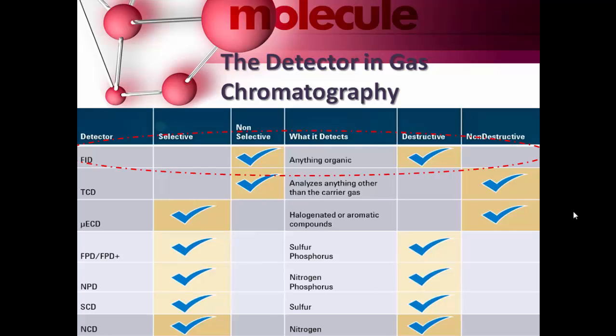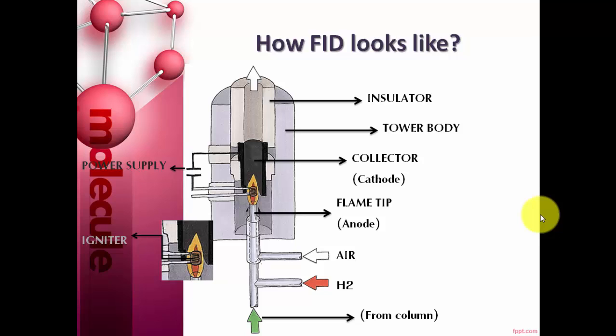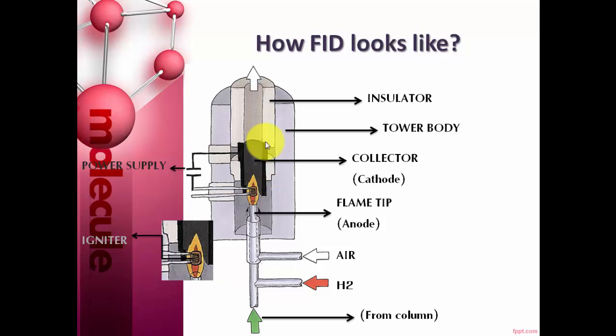The detector we are using is the FID. The FID is a non-selective detector which detects anything organic, and it uses a destructive process. The FID works by directing the gas phase output from the column into a hydrogen flame. A voltage of 100 to 200 volts is applied between the flame and an electrode. That electrode is called a cathode, while another electrode placed away from the flame is called the anode, which is usually placed below the flame.